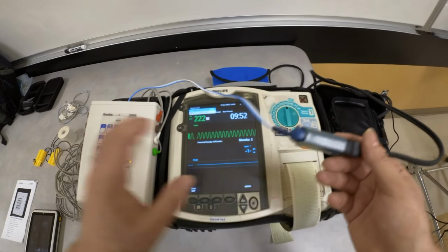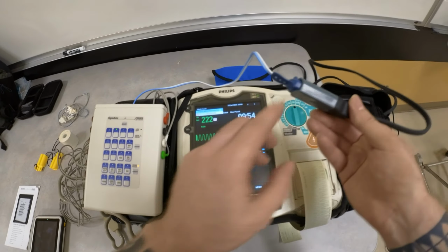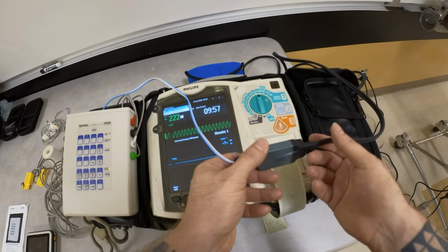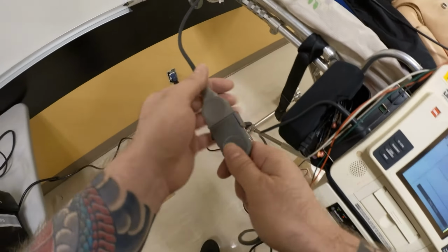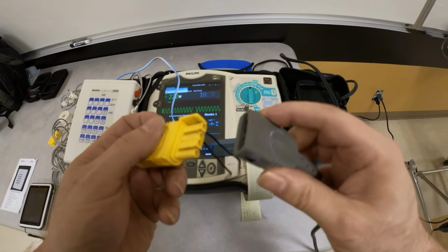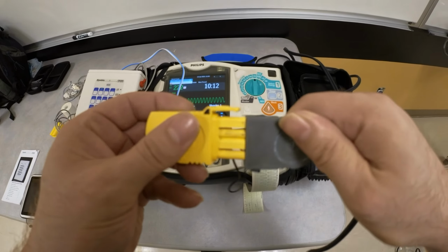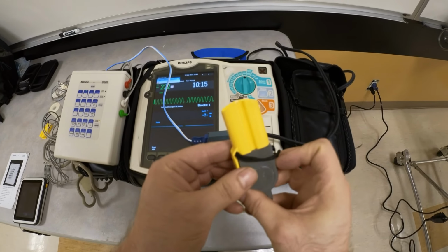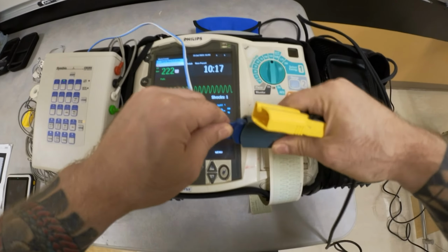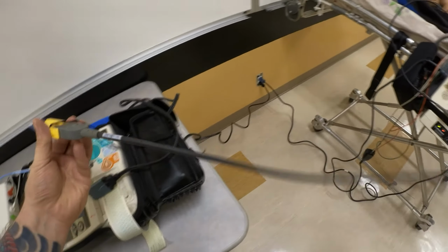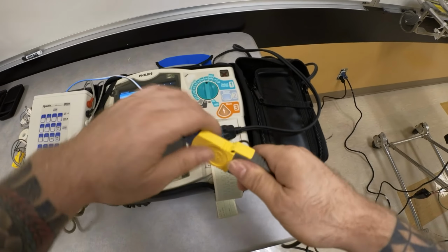Be cognizant that if you're using this device with MRX Philips, you do not need an adapter. However, if you were going to employ a LifePak 12, you notice, right, the connection here is different. So how would you accommodate this device? Very simple. You take this adapter and you're going to connect it like so. Once this is connected, you're able to connect it to your LifePak. So this will be the connection to your LifePak device. You basically need this yellow adapter to interconvert. So we'll get back to this in a moment.